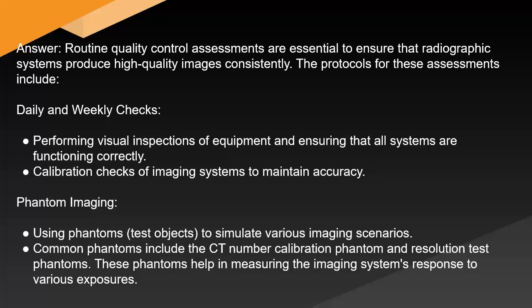Phantom imaging, using phantoms, test objects, to simulate various imaging scenarios. Common phantoms include the CT number calibration phantom and resolution test phantoms. These phantoms help in measuring the imaging system's response to various exposures.